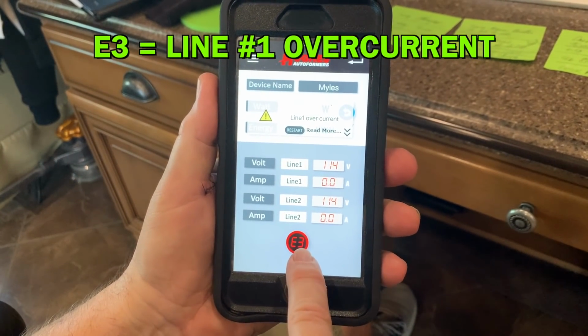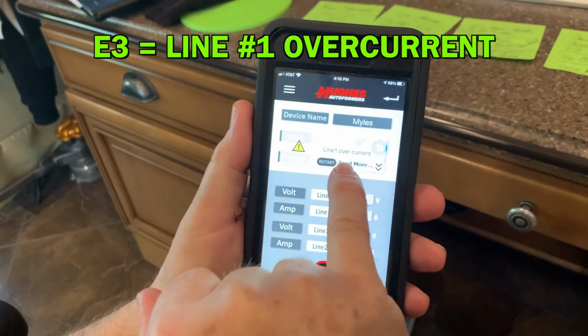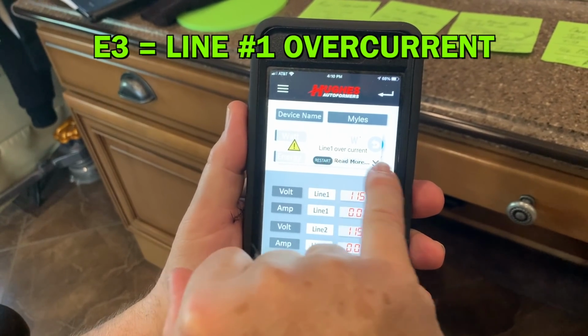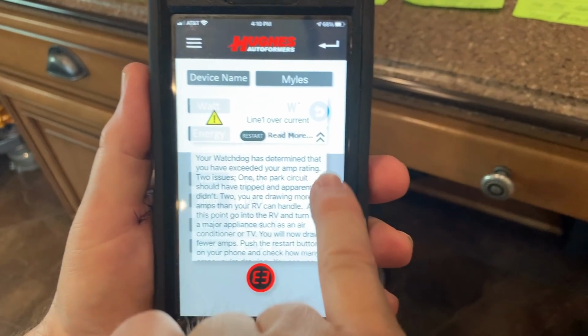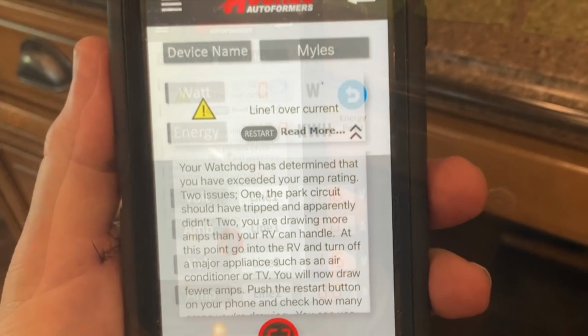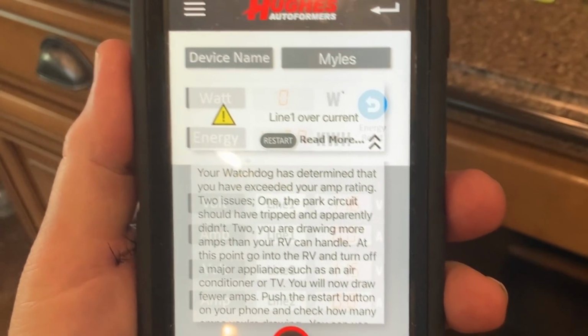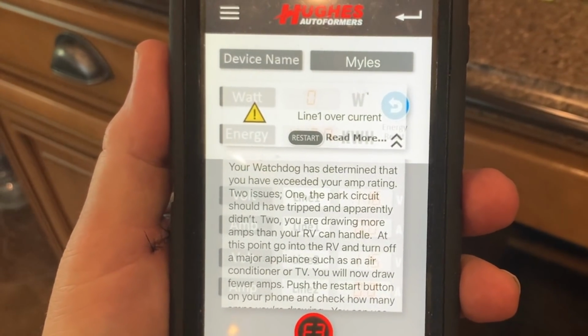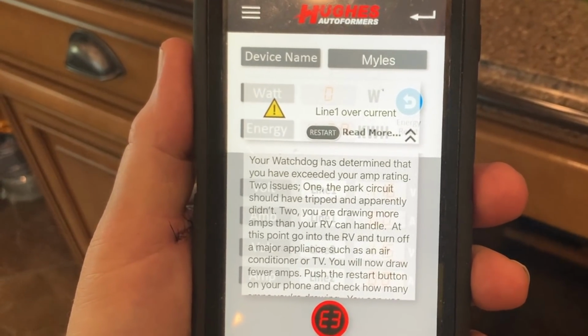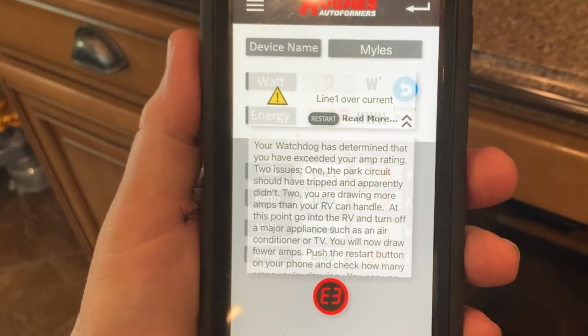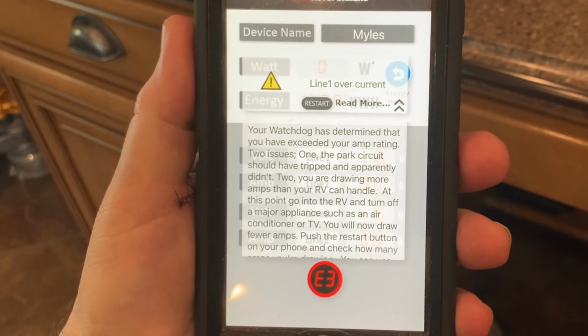Let's see if it does. It does not. Okay, I want to hit this line 1 overcurrent restart. I could read more: your watchdog has determined that you've exceeded your amp rating. Two issues: one, the park circuit breaker should have tripped and apparently didn't; two, you're drawing more amps than your RV can handle.